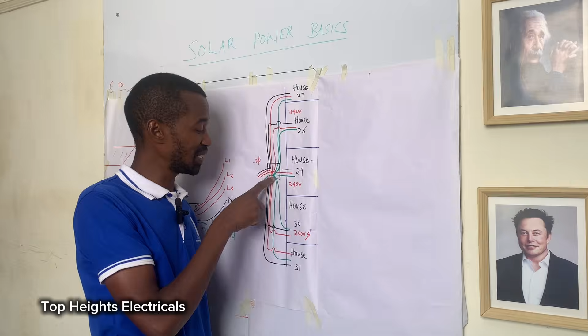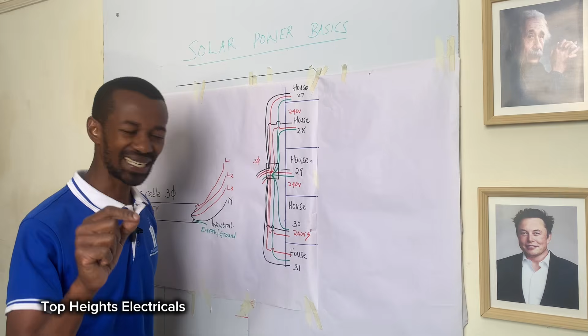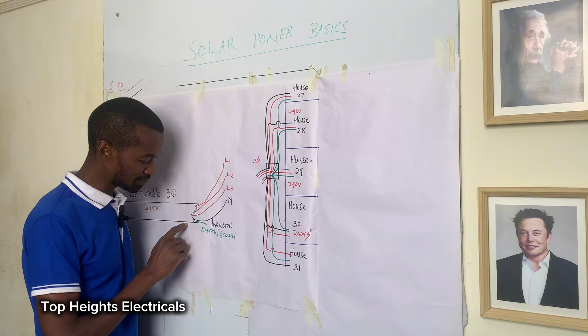Each and every unit you see here was also terminated at this point. But remember, this cable has a metallic sheath. What was happening is that this metallic sheath was acting as the earth or ground, and this termination was connected to all of these conductors, serving as the earth connection.